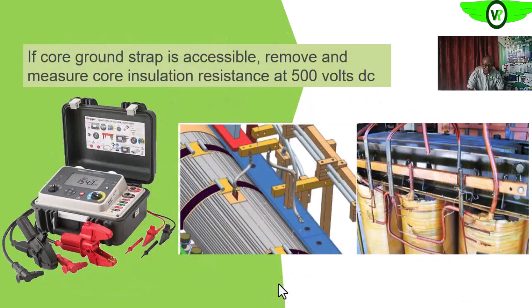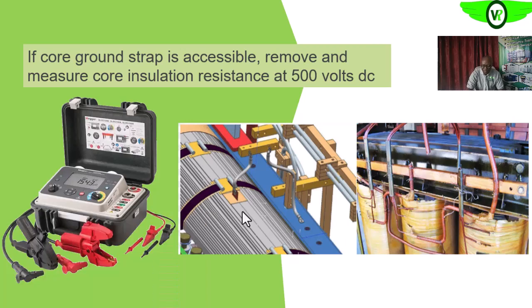So the next, we want to look at the core to see that it is not shorted. If the grounding strap is accessible, we can disconnect the grounding strap and test for the insulation between the core and ground, and between the core and any of the terminal connections if it is accessible. If not, we can actually let this go.